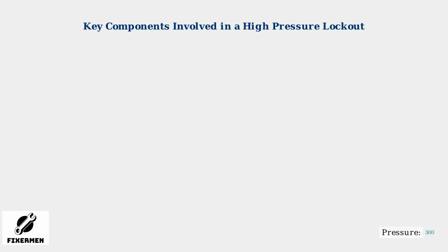When a lockout occurs, pressure builds up in the system. The high-pressure switch monitors this pressure. Error code 45 appears on the thermostat or control board, accompanied by flashing LEDs to alert the user. Identifying these components helps in pinpointing potential problem areas for troubleshooting.